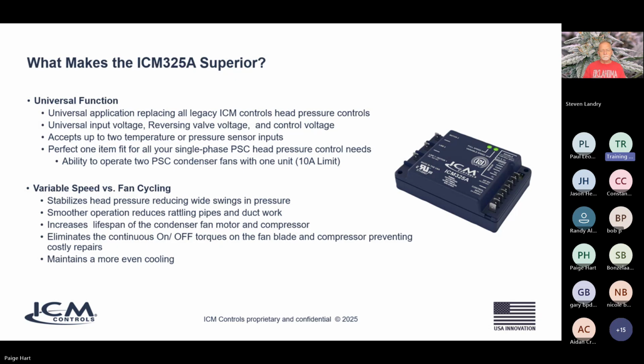And don't forget, it has the ability to operate 2 condenser fan motors up to a 10 amp limit. So that's another question a lot of people ask when they call in technical support: hey, can I run 2 fans off of this? Yes, you can. As long as you keep the commons of both of those fans in parallel with the motor 2 output, then yes, we will control both of those fans at whatever speed the pressure sensor or transducer is telling it to do so.